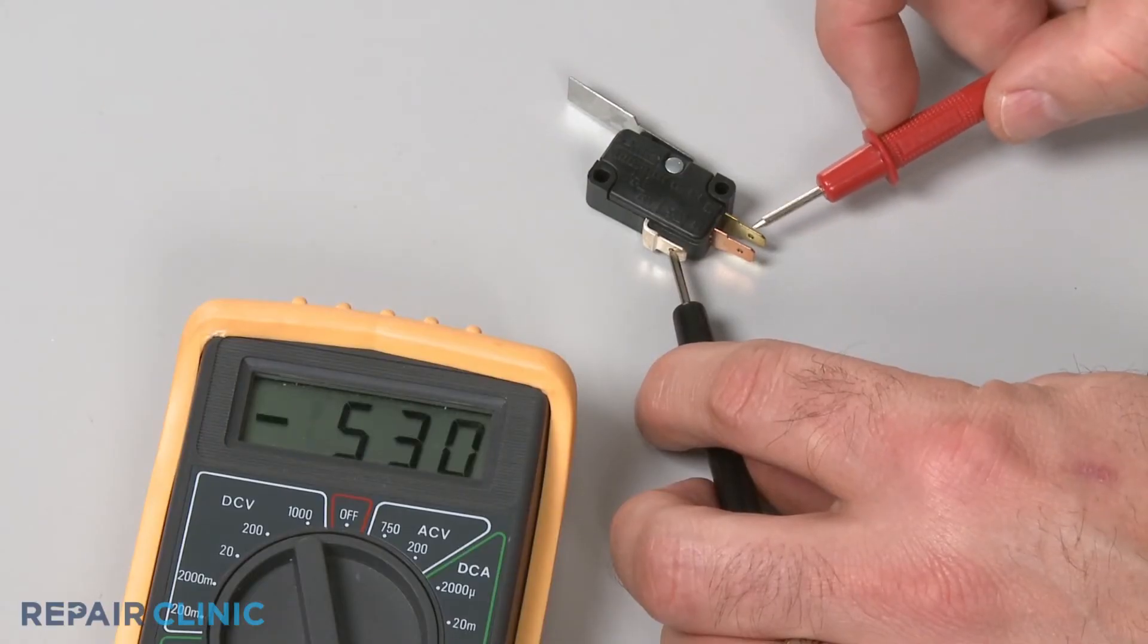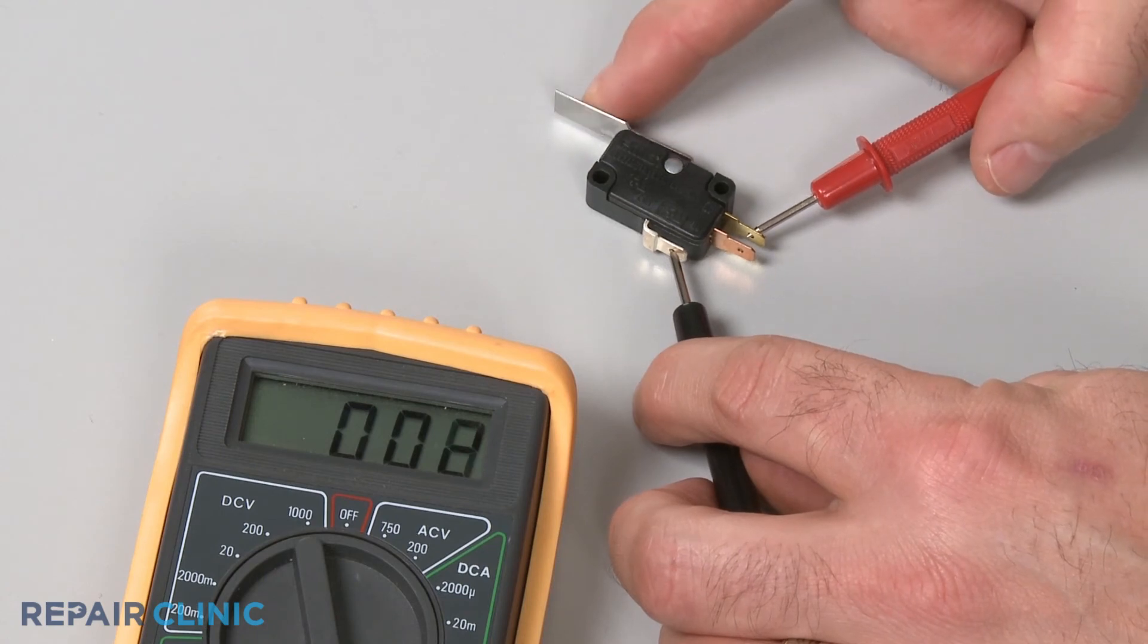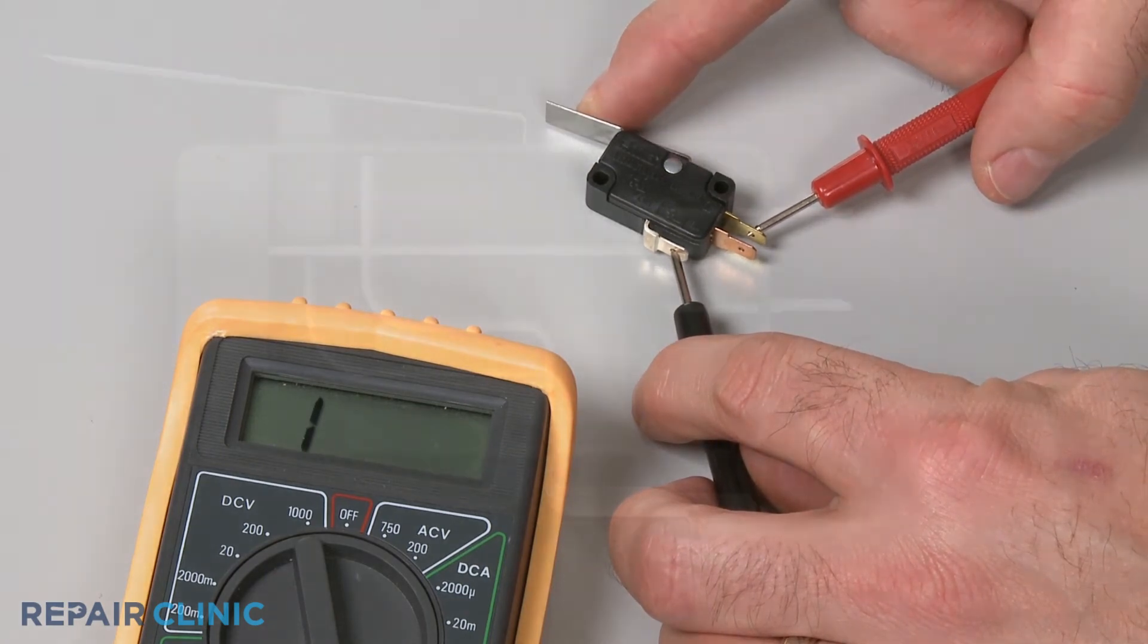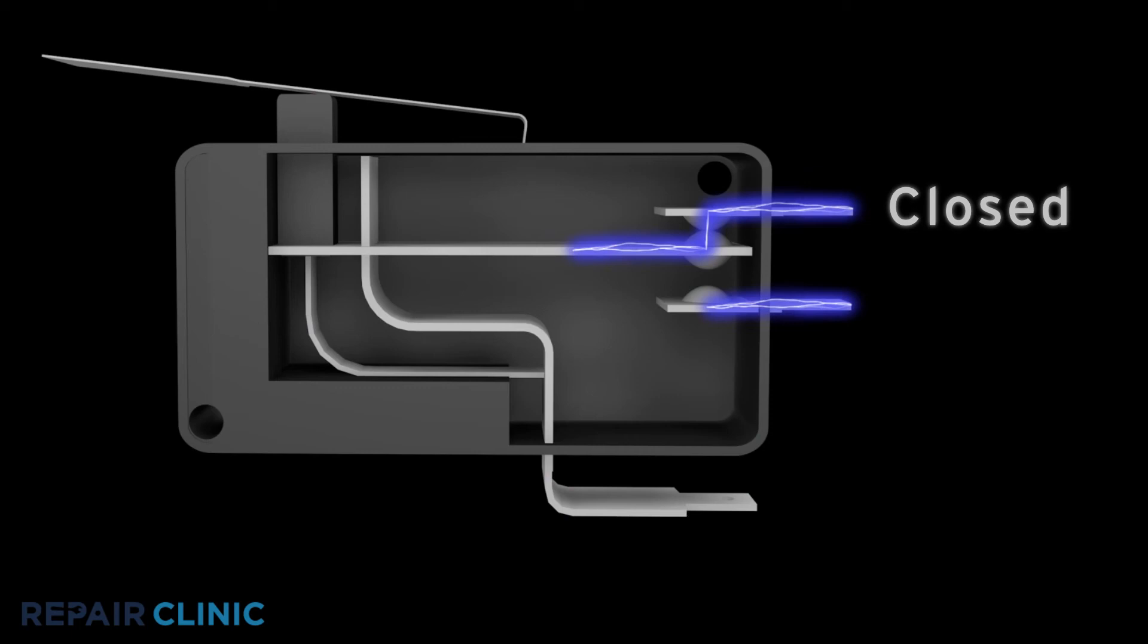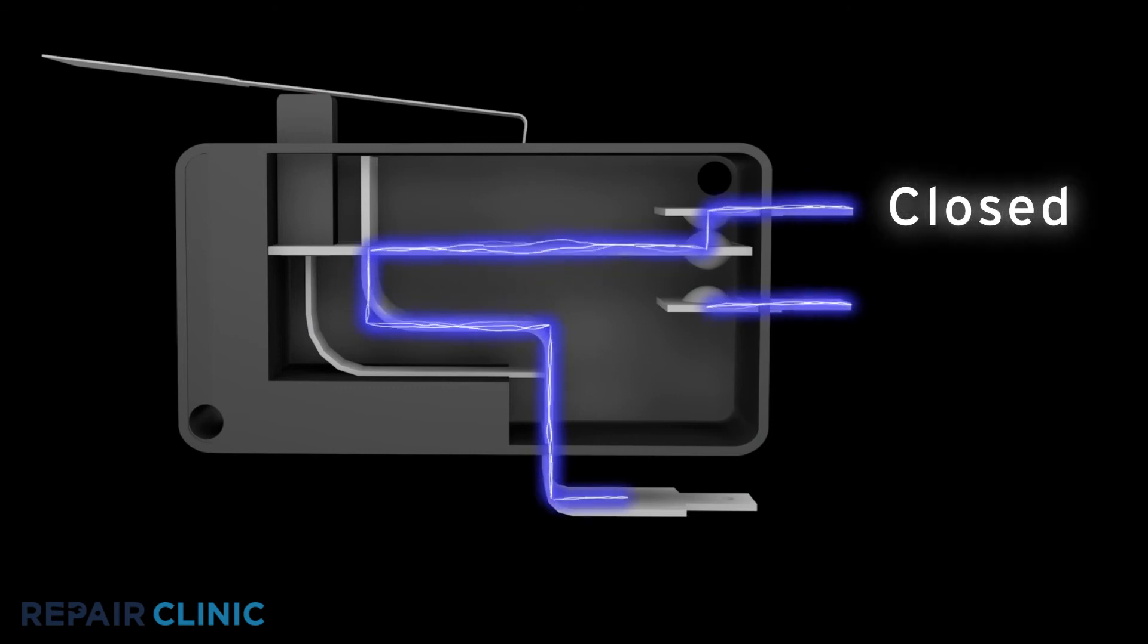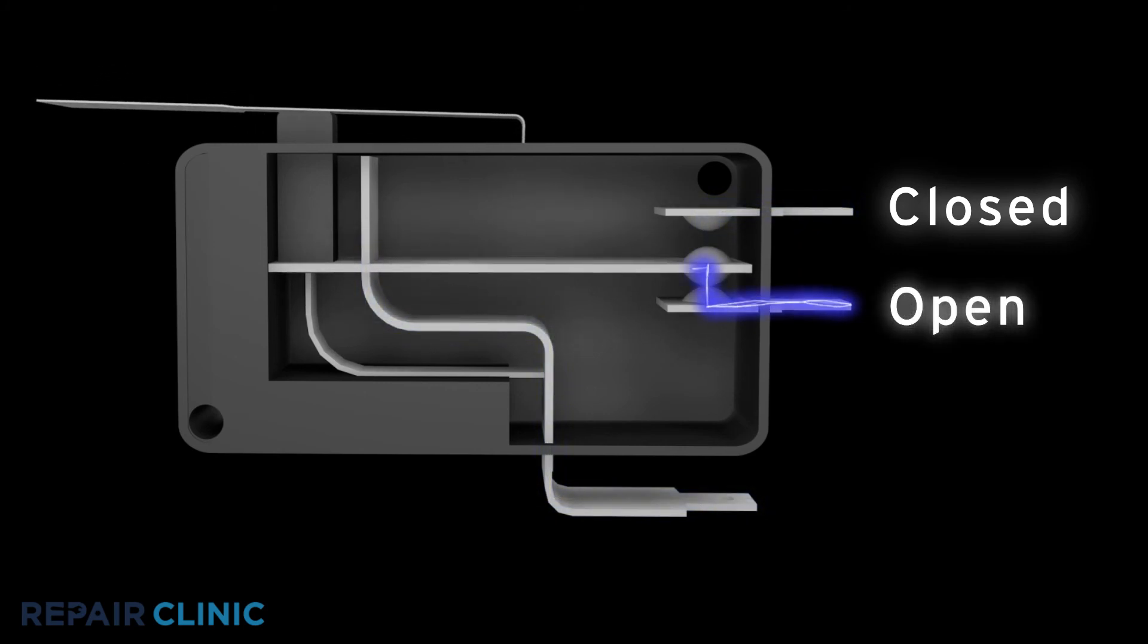Repeat the test for the normally closed terminal to determine if it has continuity. Keep in mind that the normally closed terminal should only provide continuity before the switch has been actuated. Likewise, the normally open terminal should only provide continuity after the switch has been actuated.